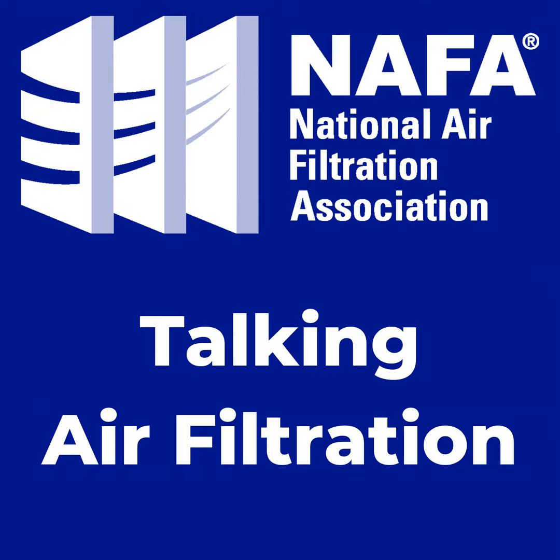And then on the bottom, you see the depth of the filter media. So with the glass, you have that depth mechanism. That's how the filter really works. But with the PTFE, you've got just the two support layers and then a really thin membrane in the middle there. And the benefit of using the PTFE is you can get a much lower pressure drop and you can get the same filter performance with it.